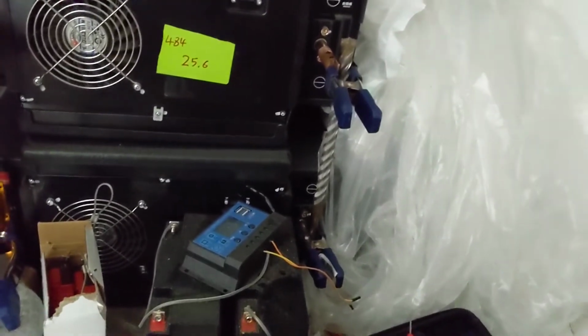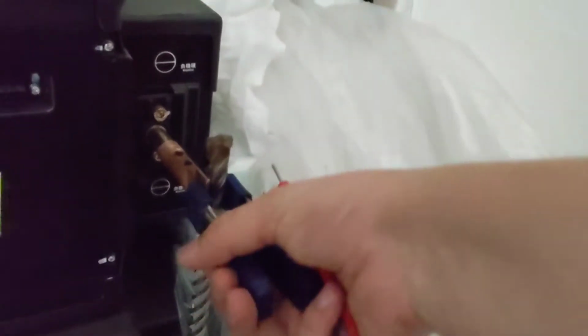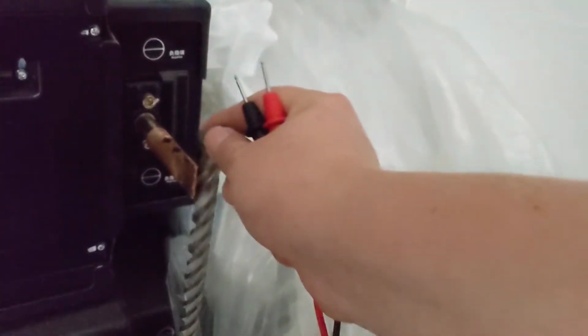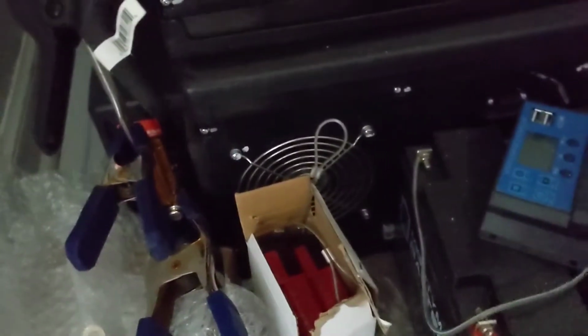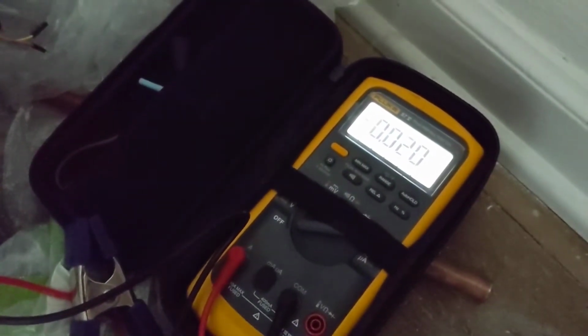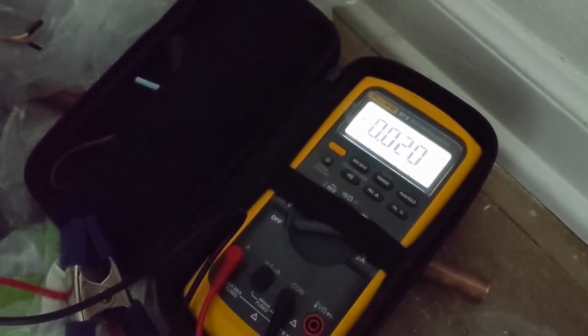I should have done this before, usually you'd want this to sit for 12 or 24 hours. So I don't know really how well these were matched before, but what I've done as a little test is broken this circuit, so here they are not loaded from one to the other anymore through this resistor. So I've got an open circuit. I've got my Fluke 87V, so we're just going to do a quick current draw test. We're now completing the circuit using the meter, and we see we've only got like 20 milliamps of current moving.